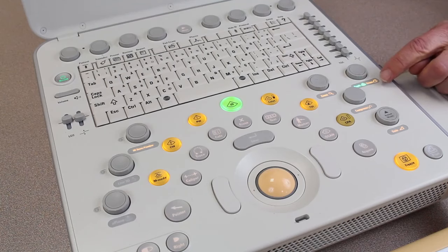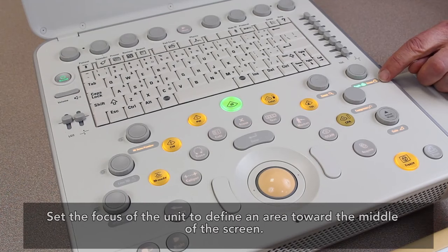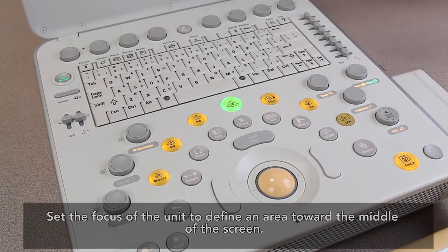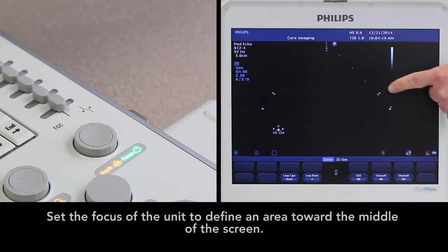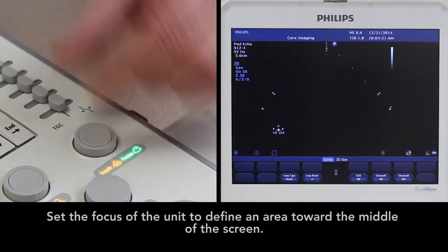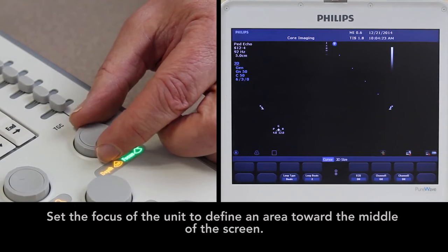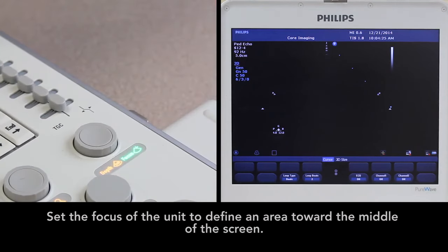The next thing we might want to adjust is the focal spot for imaging, which on this machine is adjusted with the same knob used to change the imaging depth. The optimal focal spot for the image is identified here by this dot on the screen. This focal spot is the level where the best echocardiographic image will be obtained, so you'd like to adjust the focal zone to the area of interest, which for our exam will be the level of the left atrium and the left ventricle.